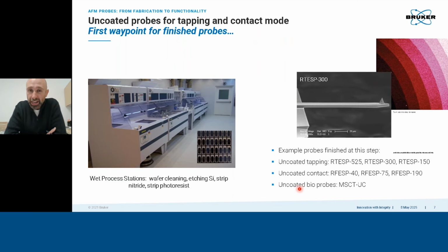Okay. So if you just do that, then you've already got some probes that you could pretty much stop at that point and qualify them, and then they're ready to sort of use. So an example of that is, again, sort of mentioned on the previous slide, an RTESP 300, and various other probes like that in the range. So in the bullet points here, you can see an uncoated tapping probe, an RTESP-525, that's a 500 kilohertz tapping probe, a 300, a 150, and others like this. Those are probes that can be used in tapping mode for regular imaging in air. We also make contact probes that can be like this, so an RFESP 40 or -75, and again, sort of more that are used in contact mode.